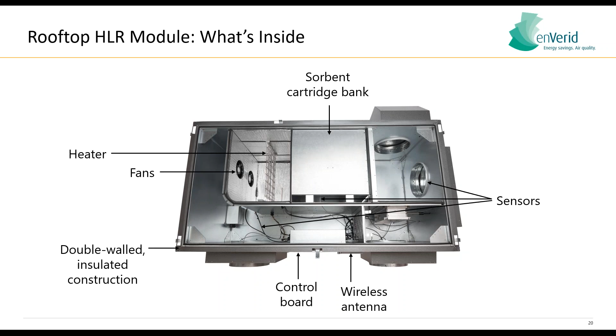So how does it work? The HLR has two modes. The first mode is adsorption. So adsorption of contaminants: you get indoor air, the fans are working, it goes through the sorbent and goes back through the green damper on top to the air handling unit, return duct or plenum. What does it capture? It captures carbon dioxide, and this is the main forte of the technology, formaldehyde, also the main differentiator of the technology, and also VOCs, ozone. It does remove odors, and it has zero byproducts.